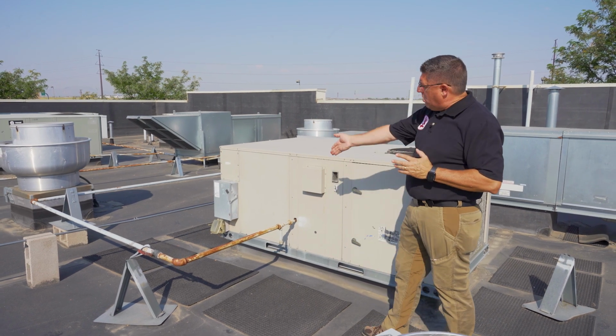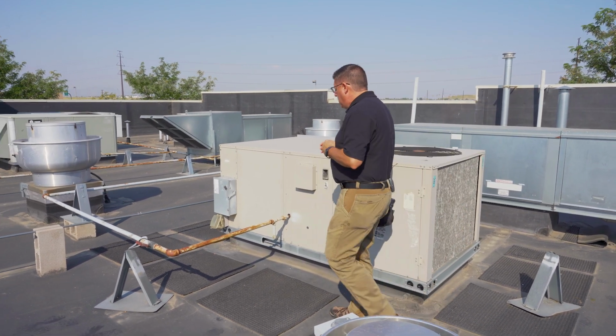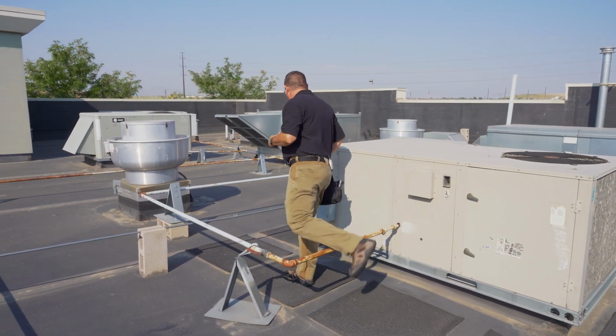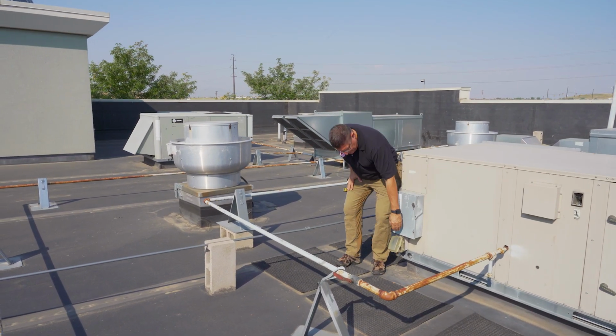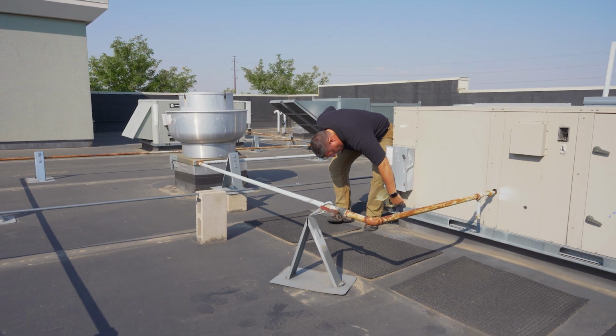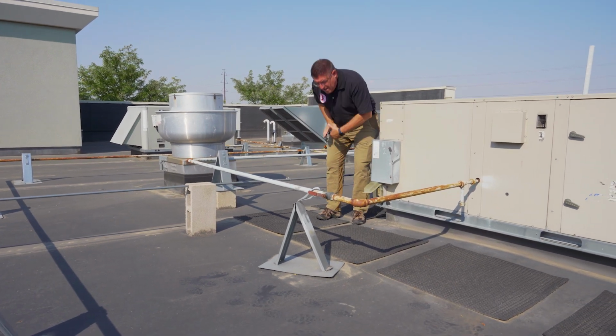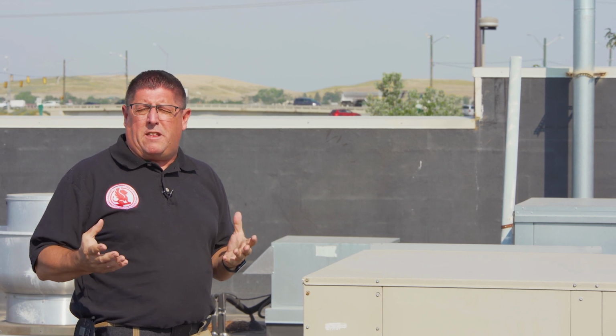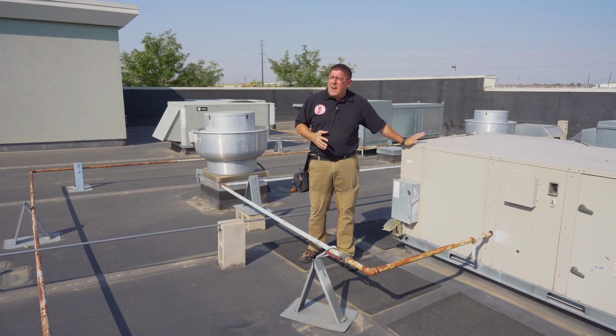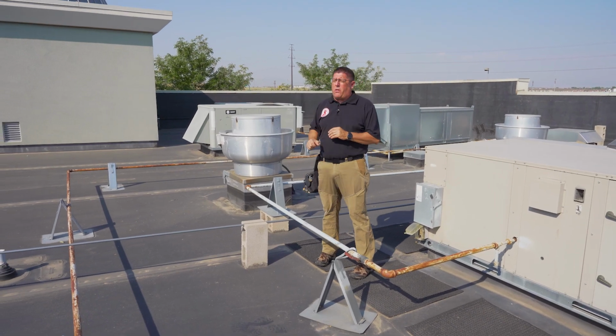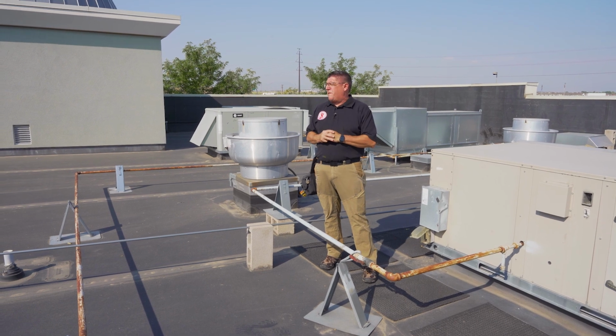And then as we travel through, we do have our convenience outlet. We want to make sure that that operates. In this particular case, I've got the outlet right here, and then I trip and reset it, and it trips perfectly. There's not really a standard for how many should be there. There just needs to be an outlet that's up in the space to operate these units. In this particular roof, I've got an outlet on this appliance, I've got an outlet on another appliance, and then I've got another outlet a little further down.